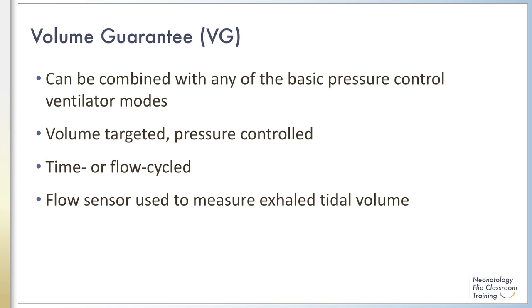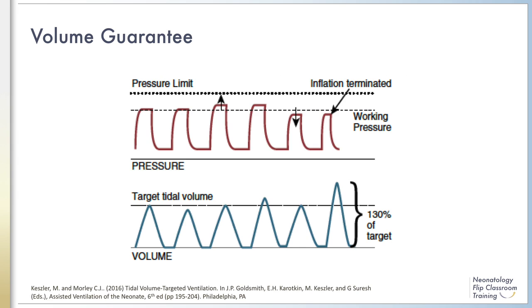Volume guarantee mode can be either time-cycled or flow-cycled depending on whether it is used with SIMV, AC, or PSV. A flow sensor is used to measure flow at exhalation to determine the exhaled tidal volume and adjust inspiratory pressures to target the desired tidal volume. The clinician sets the targeted tidal volume and a pressure limit. The ventilator compares the exhaled tidal volume from the previous inflation and adjusts the pressure up or down. The machine limits pressure increments to a maximum of 3 cmH₂O change per breath.